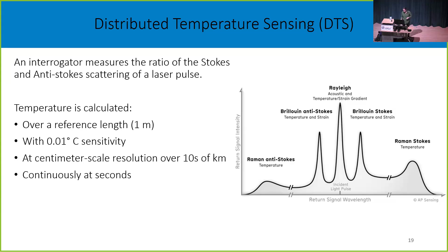And I just want to re-emphasize that with DTS, one of the challenges, but also one of the really fascinating pieces, is that the calibration is key. So the instrument itself is not really putting out a meaningful environmental signal. It's giving you the ratio of two signals. And a key part of deploying any DTS system is basically running portions of your fiber optic cable through reference baths where you're controlling the temperature, and then using those controlled segments of the cable to develop a specific calibration for that cable type and environment. And then you can use that calibration to get a really high fidelity measurement of temperature all along the cable.